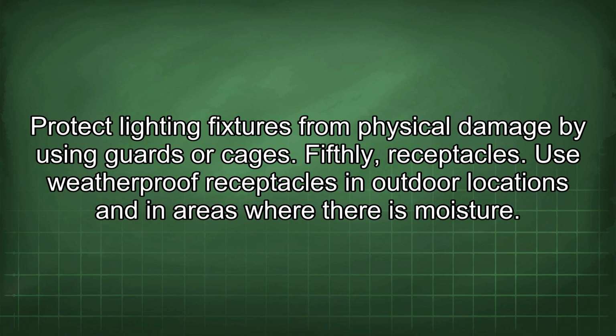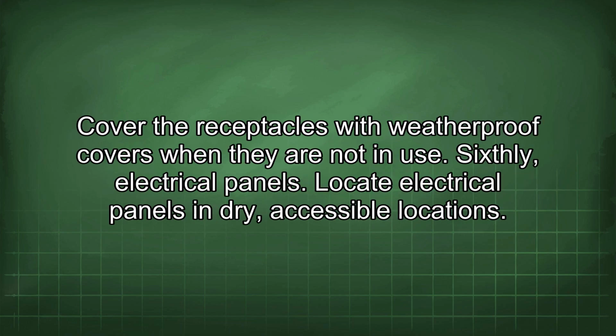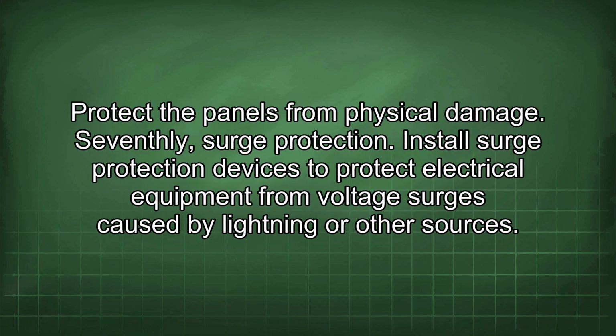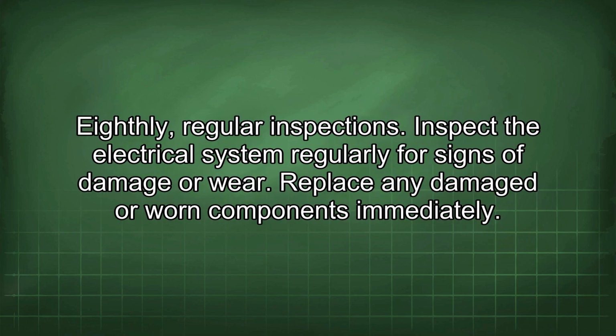Fifthly, receptacles. Use weatherproof receptacles in outdoor locations and in areas where there is moisture. Cover the receptacles with weatherproof covers when they are not in use. Sixthly, electrical panels. Locate electrical panels in dry, accessible locations. Protect the panels from physical damage. Seventhly, surge protection. Install surge protection devices to protect electrical equipment from voltage surges caused by lightning or other sources. Eighthly, regular inspections. Inspect the electrical system regularly for signs of damage or wear. Replace any damaged or worn components immediately.